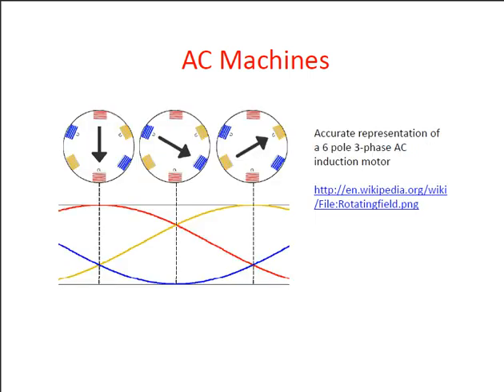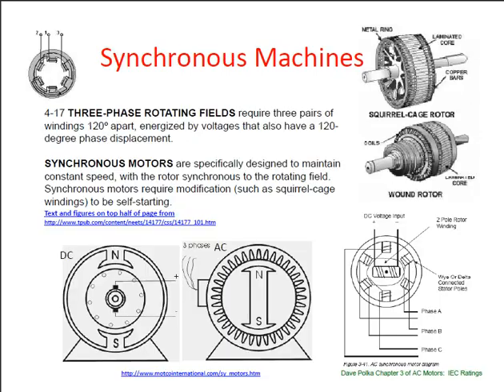An accurate representation of a six-pole three-phase AC induction motor. For a synchronous machine, a three-phase rotating field synchronous motor requires three pairs of windings 120 degrees apart, energized by voltages that also have 120 degrees phase displacement. Synchronous motors are specially designed to maintain constant speed. To fit the rotor synchronously to the rotating field, synchronous motors require modifications such as squirrel cage windings to be self-starting.